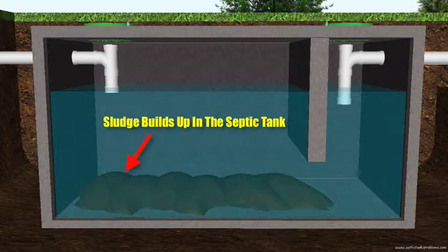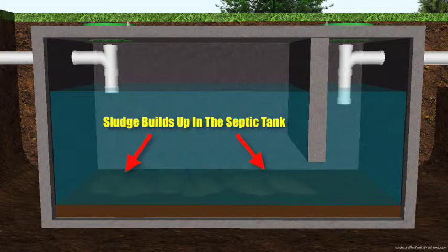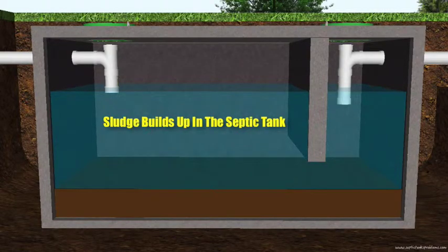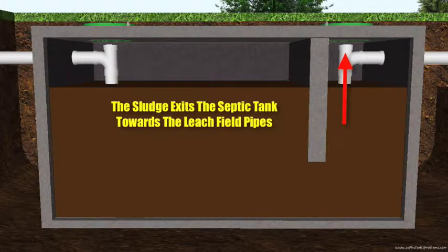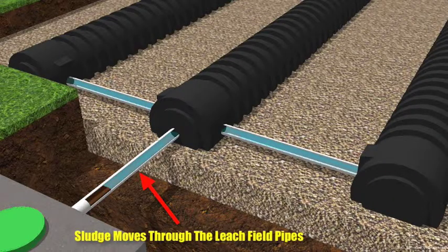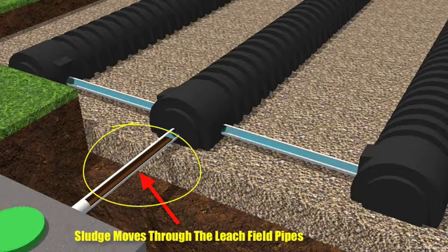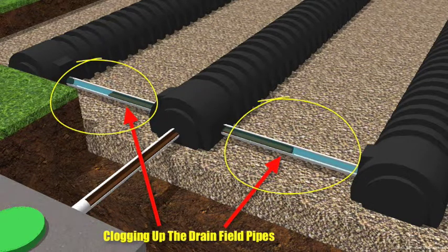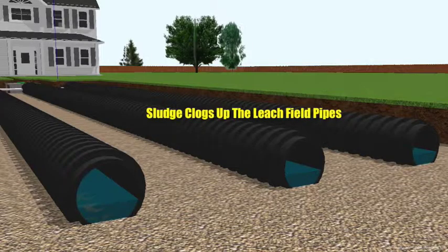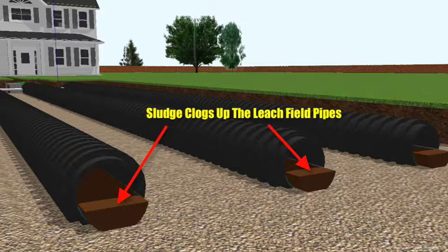The biggest problem with every septic tank is sludge. Over time, solids settle on the bottom of the septic tank. If the tank isn't pumped out regularly, this sludge builds up and eventually exits the septic tank toward the drain field pipes. The sludge makes its way through the small connecting pipes and completely clogs them, restricting wastewater flow. When sludge reaches the drain field pipes, it clogs the entire system, trapping wastewater so it can't be discharged or treated in the gravel or soil.